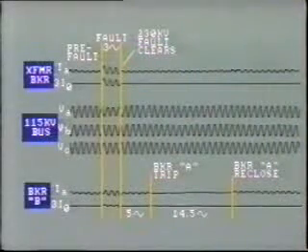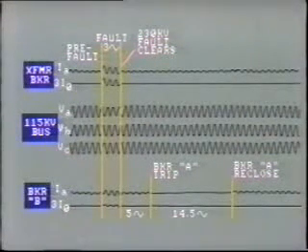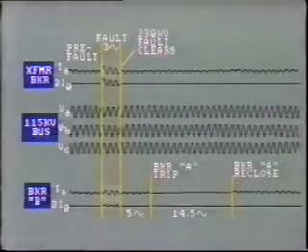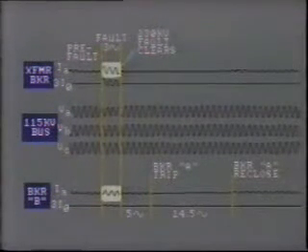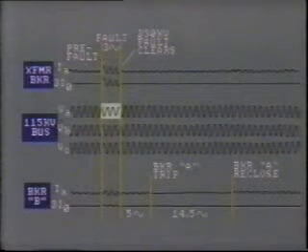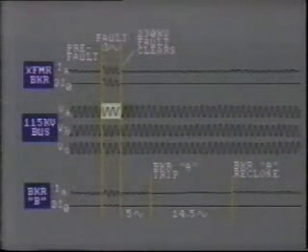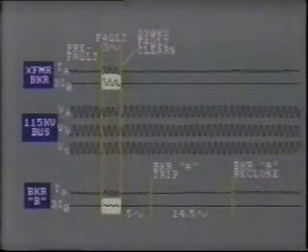You can see the onset of a single line-to-ground fault on the 230 kV line. The fault was on A phase, as shown by the sharp increase in A phase current through the transformer breaker and breaker B, and also by the depressed A phase bus voltage. The presence of zero sequence in the breakers also indicates a ground fault.